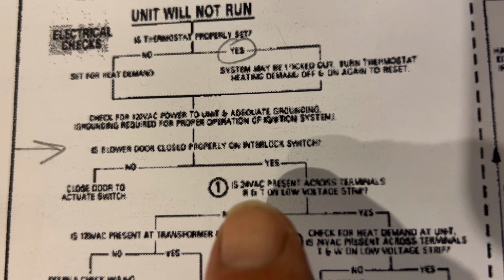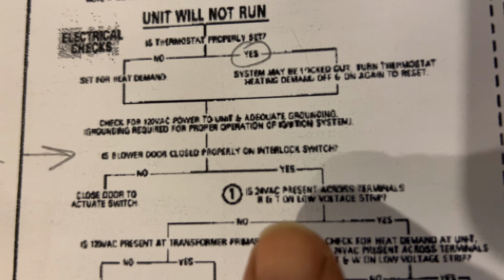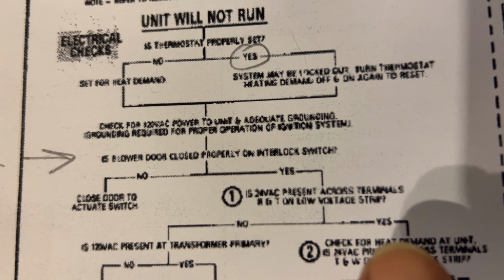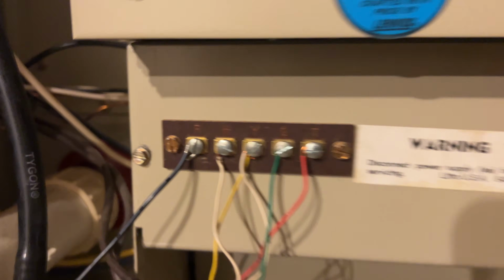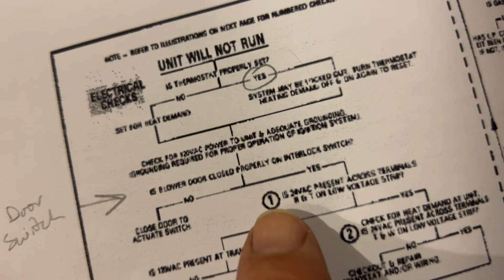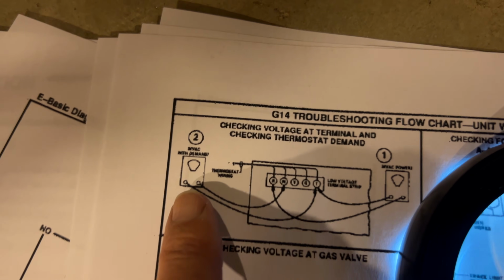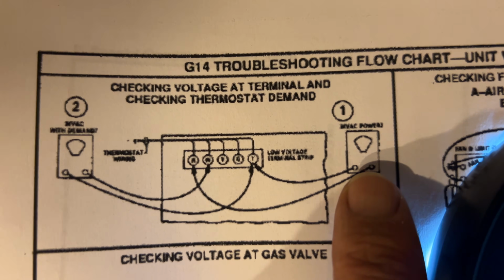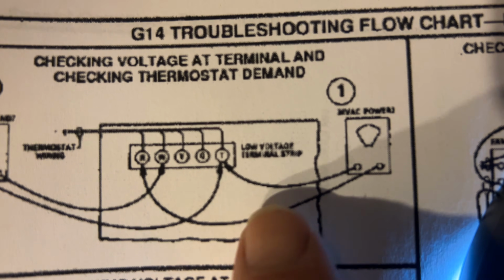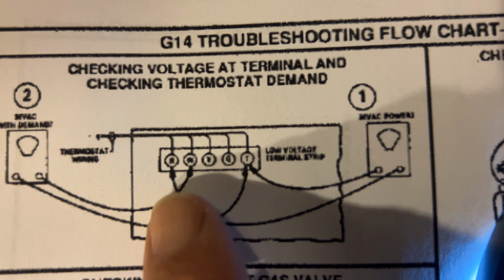It's kind of hard to read, but I believe that says R to T on the low voltage strip. So this is our low voltage strip right here, and we're gonna measure. It actually gives us a reference number, see the little reference number right here? That's referenced on the following page where we have this. So this is number 1. We have to test from T to R, so we'll check that right now and see if we got 24 volts.